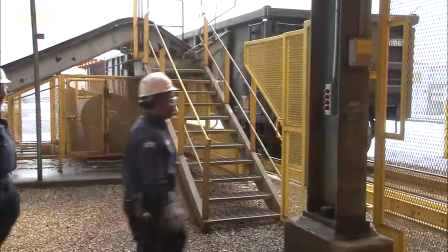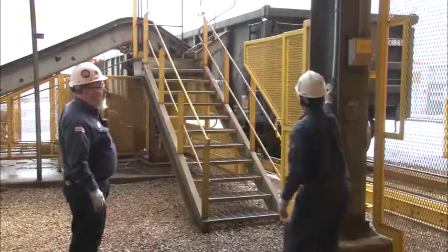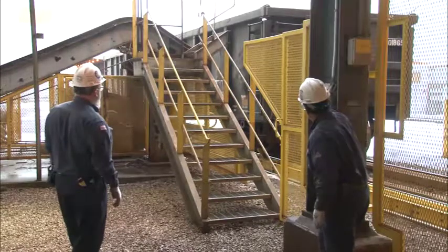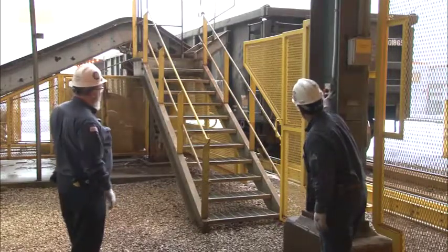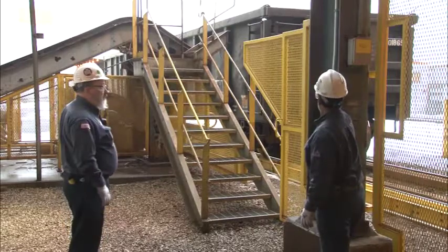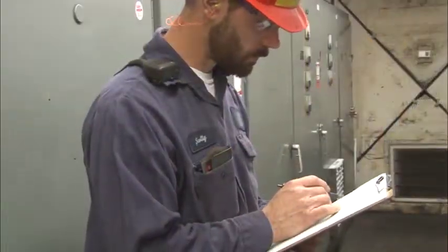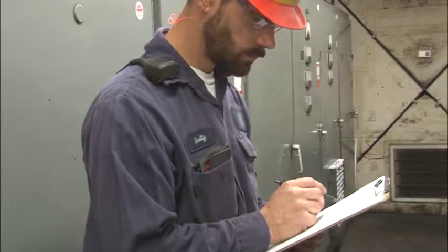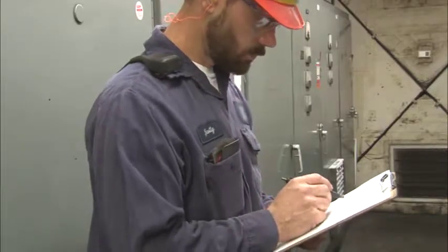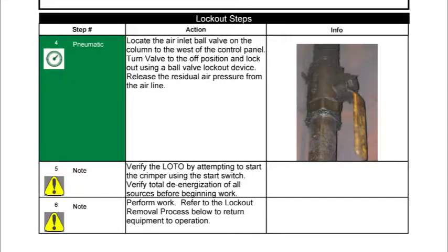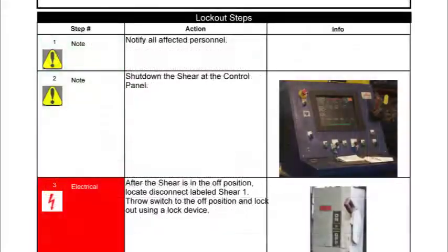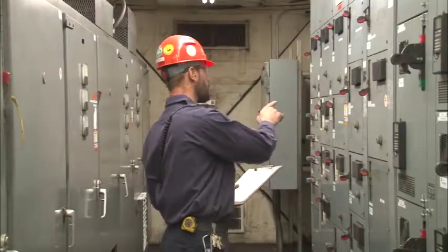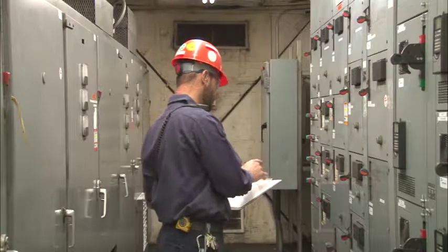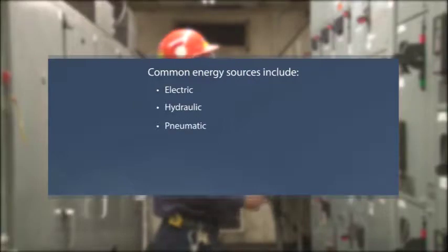The first step in lockout, tagout, tryout is to notify all employees and contractors affected by the lockout that the equipment is going to be shut down and that they will need to participate in lockout activities. Once all personnel are notified and aware of the lockout, the specific energy control procedure involved must be reviewed. This procedure is unique for every piece of equipment and is a step-by-step guide on how to lock out the piece of equipment being worked on. The lockout, tagout, tryout procedure will also help identify all energy sources involved. Common energy sources include electric, hydraulic, pneumatic, and gravity.